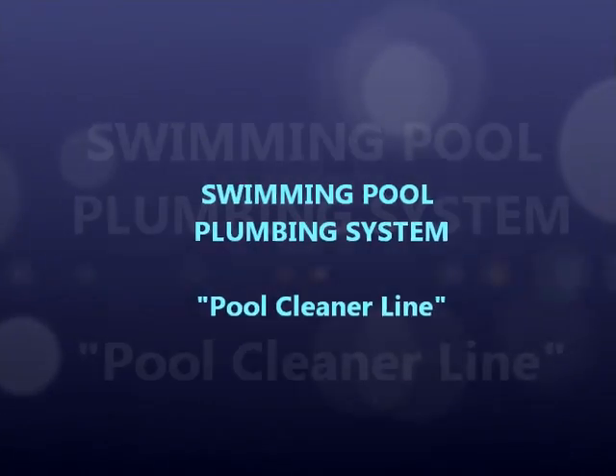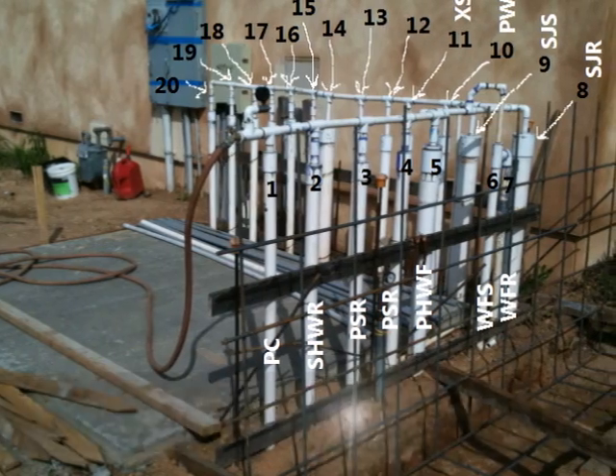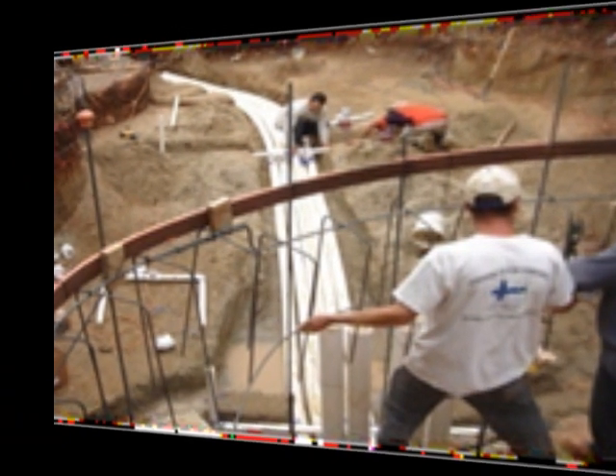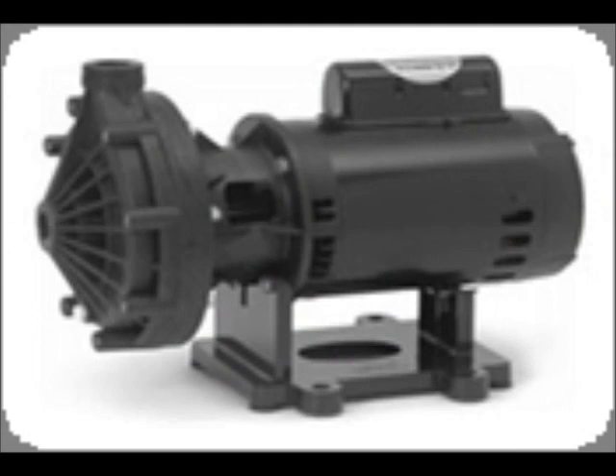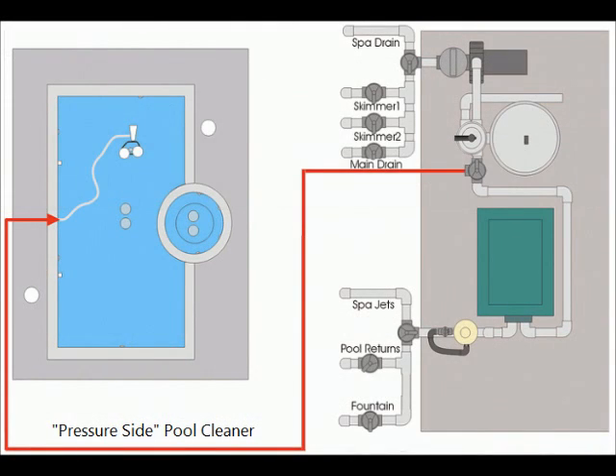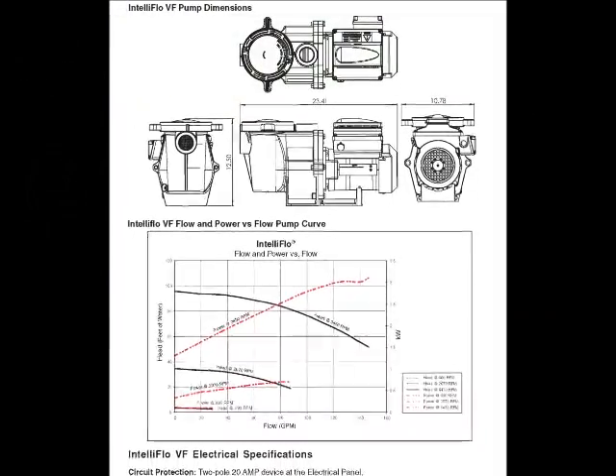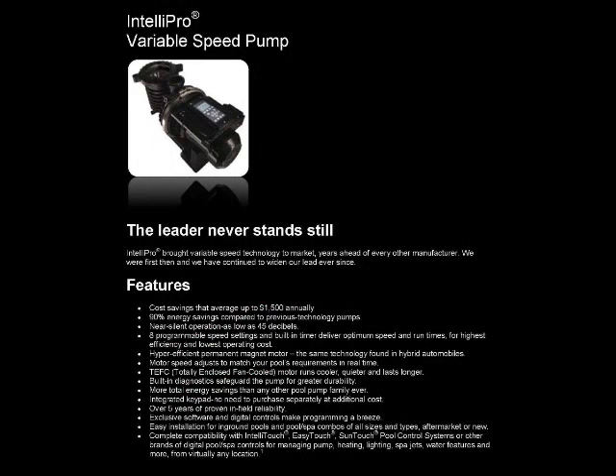In planning and preparing for the distribution of the swimming pool's piping network, the termination of these piping considerations will involve anticipation and designation of the operational functionalities being conscripted to the desired pool functions. In making these determinations, one of the choices will be to utilize a pressure-side pool cleaner or a suction-side pool cleaner. If a pressure-side cleaner is desired, then a 3/4 horsepower booster pump will be required, and this pump will run simultaneously with the filtration pump during the filtration mode of operation. Because the cleaner booster pump is required to run in conjunction with the filtration pump, it is our recommendation to utilize a suction-side cleaner instead for several reasons.